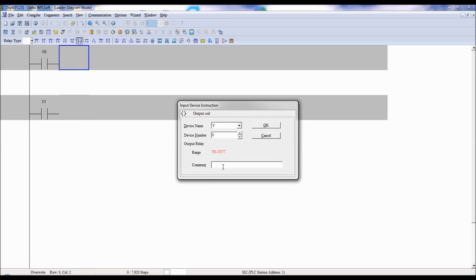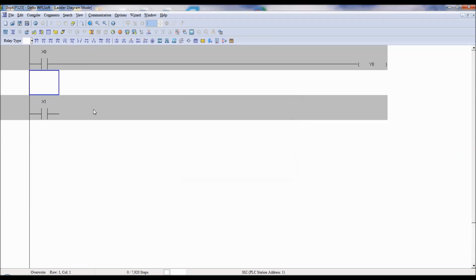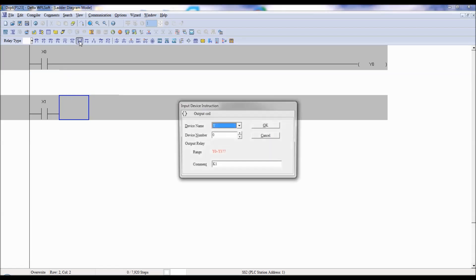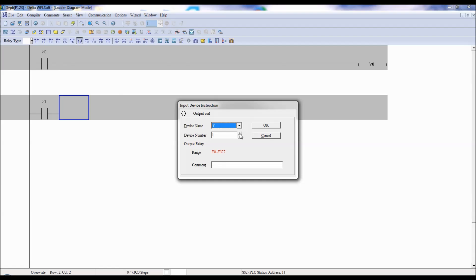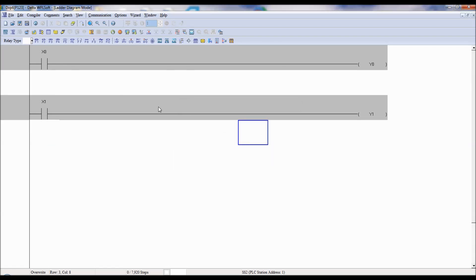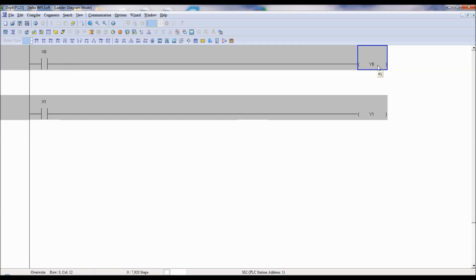Again F7 — that is Y1. Y1 is used to switch on the K2 relay. So, since we are controlling the direction: if X0 is high, Y0 is high. Y0 means K1 on. When K1 relay is on, the motor goes in one direction — say forward. If X1 is high, then Y1 is high, meaning K2 relay will be on — so that is the reverse direction.